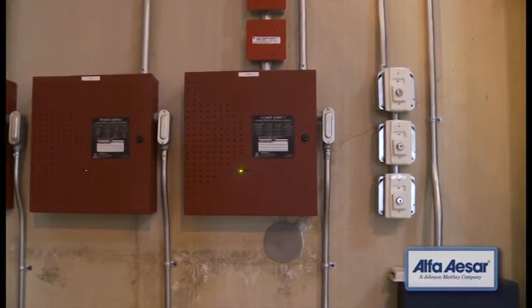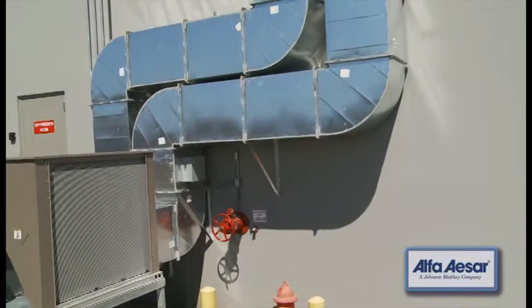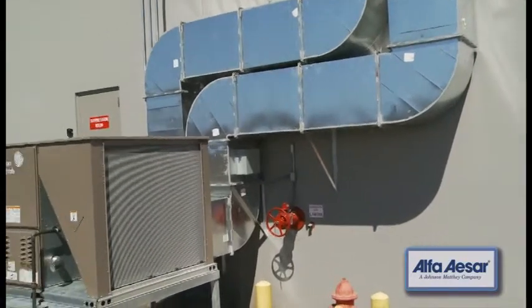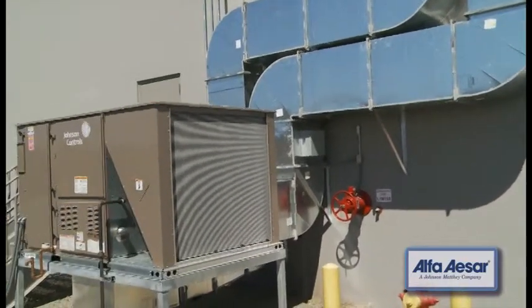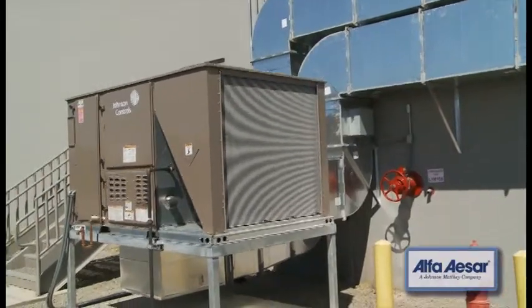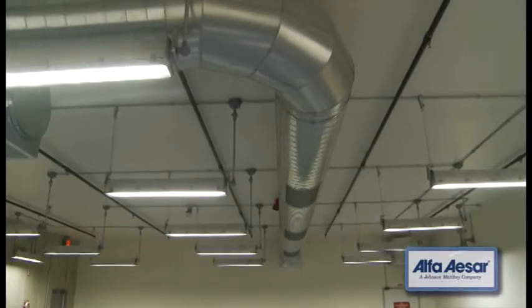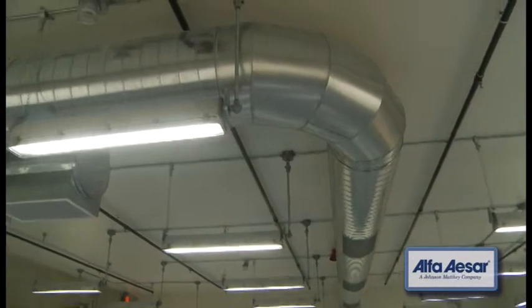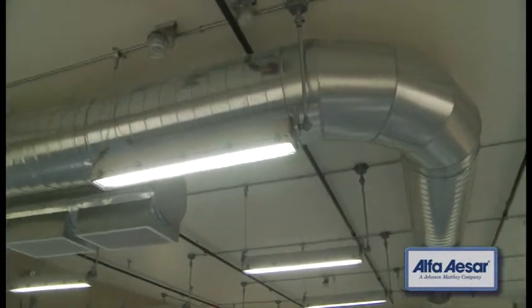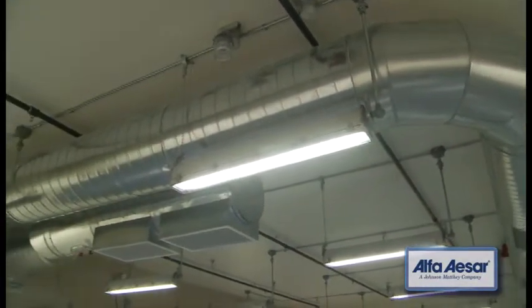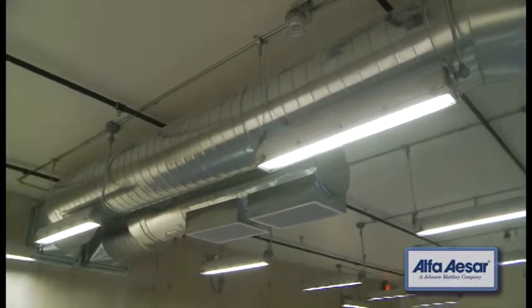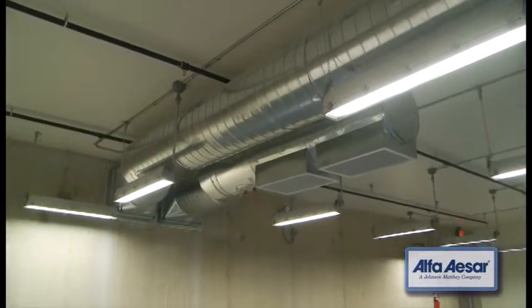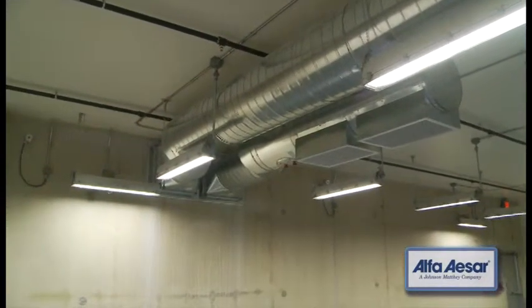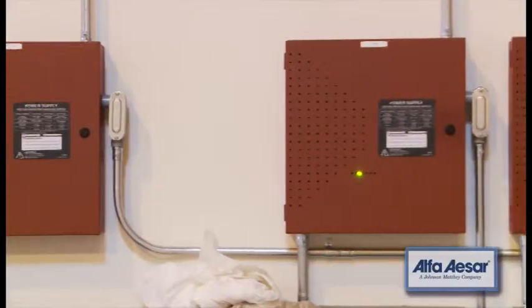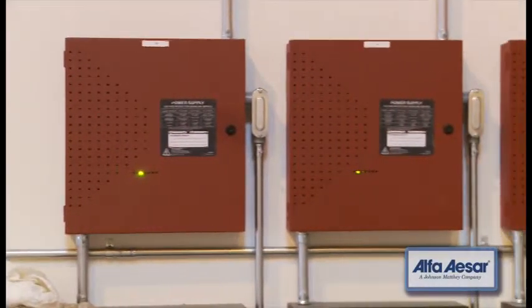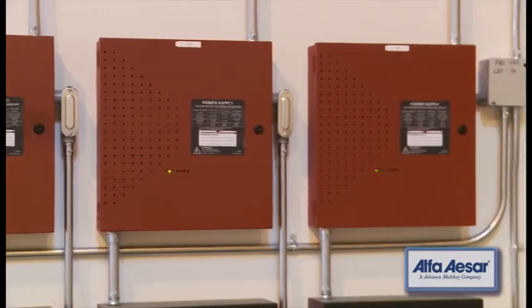Mechanical system monitoring includes duct-mounted smoke detectors to monitor supply-side ductwork of all HVAC air handlers moving more than 2,000 CFM. In some instances, this requires 2 detectors to ensure proper distances downstream from elbows, bends, and other turbulence-causing elements of the ductwork. The duct smoke detectors are provided with remote test indicator and reset buttons. These are located in corridor areas outside the space served by the associated unit and are prominently identified.